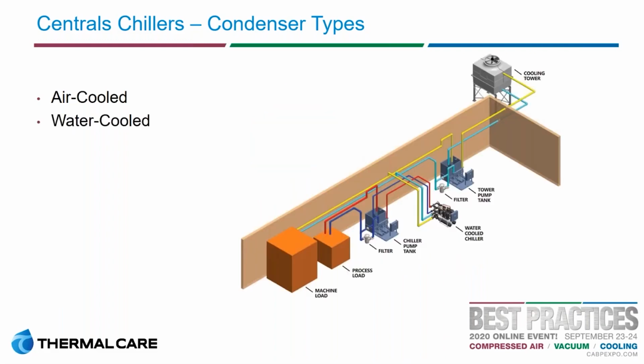Another style of chiller is a water-cooled chiller. Basically what this does is it takes away that integral fan set that we depicted on that previous slide. And so what we now have is two water loops. One of them is the chilled water loop, which is a lower temperature. And then we have the cooling tower water loop, which is a higher temperature. The cooling tower is used for the higher temperatures because it actually uses evaporation to achieve its cooling and the heat rejection. And because of that, it can only achieve certain temperatures. With a chiller, because we're using refrigeration, we can achieve much lower temperatures. So what we can do is utilize that higher temperature water to actually pull the heat out of the chiller system as well. And so what we have here is a water-cooled chiller. So there's no fans involved with that chiller. The only fan in the system is actually on that cooling tower itself, which we'll talk a little bit more about exactly how that functions.